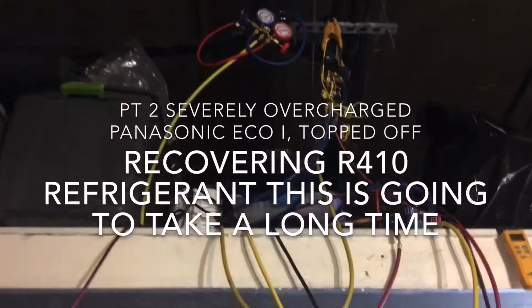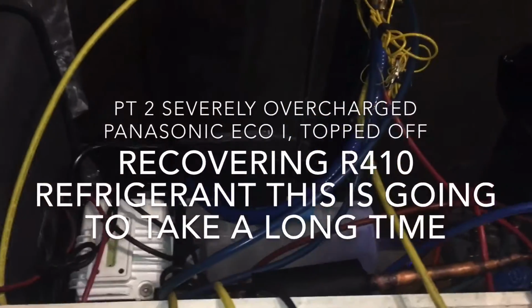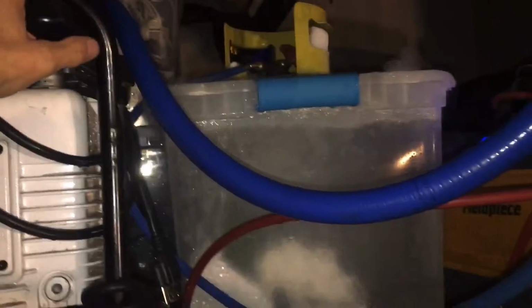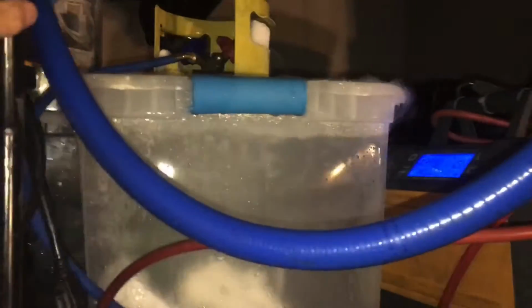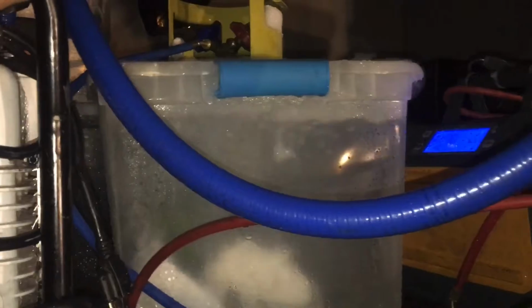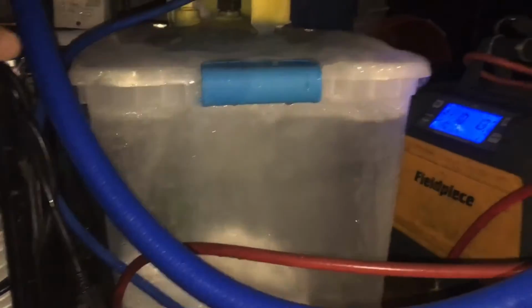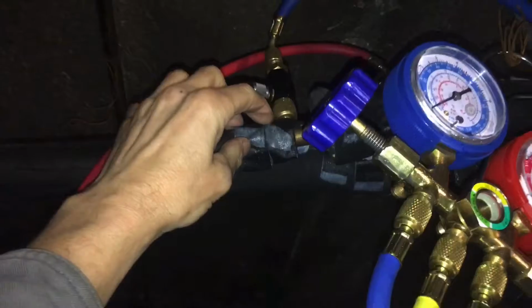Performing the recovery on this Panasonic system, and then we're going to go into vacuum. We're doing this in-house, and as you see, we're using dry ice to cool off the water because the high side pressure goes so high up in the tank. We have like 50 or 60 pounds of refrigerant to remove, and it's been raining off and on outside, so we're performing this at one of the fittings located at a ball valve on the system.